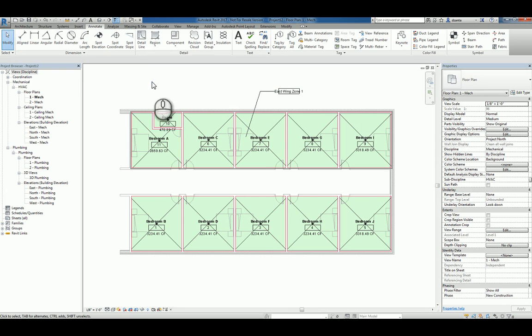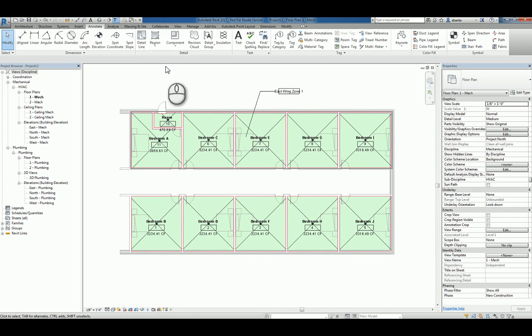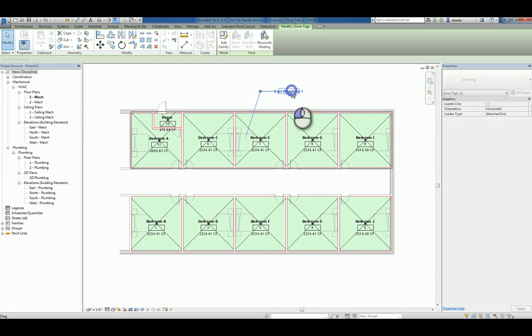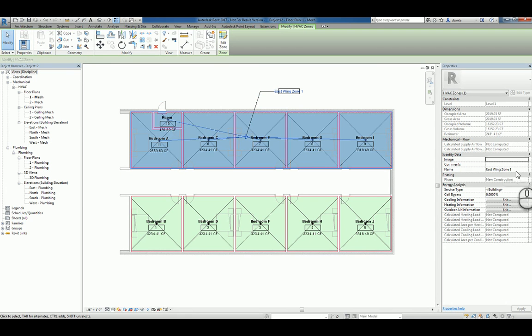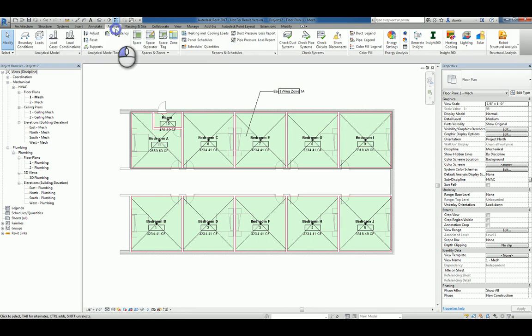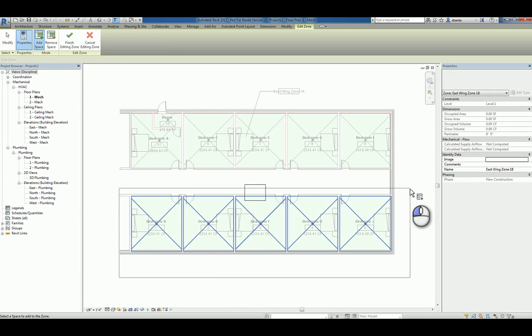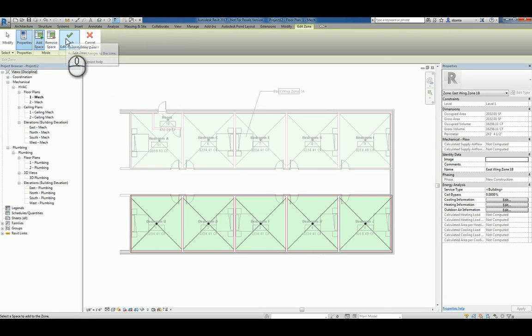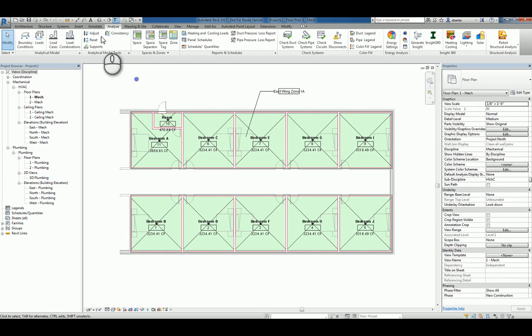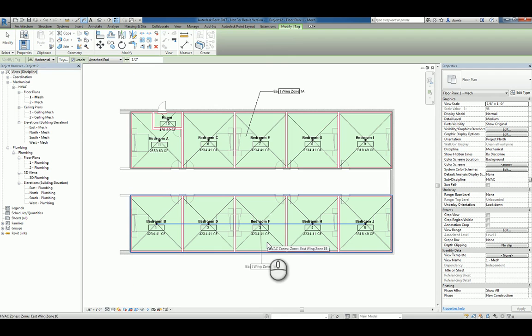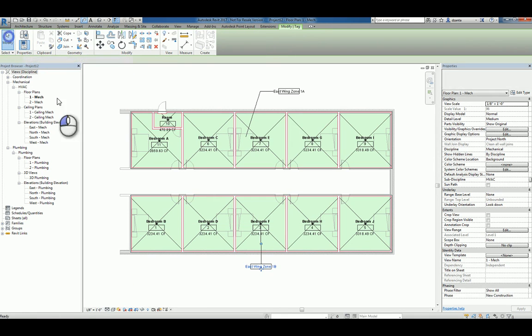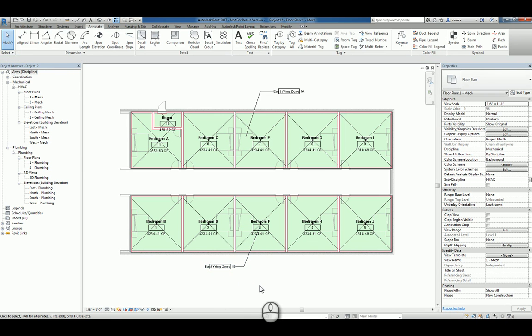Now we can do the exact same thing for the lower spaces as well as a separate zone. Or we can select this particular zone that we're dealing with and go to its properties and say East Wing Zone 1A, just to be safe. Now we'll do another zone and we'll pick the other remaining spaces. You can also just do a window selection by the way. And again, over here, East Wing Zone 1B, Revit kind of figures out what you're trying to do and gives you an automatic naming. If that's good for you, you can leave it. If you don't like it, you can change it. Hit finish editing the zone and it's created. Again, you can tag it by just putting your mouse over the object and it gets tagged. You can obviously move the tag and adjust the display so it makes sense.